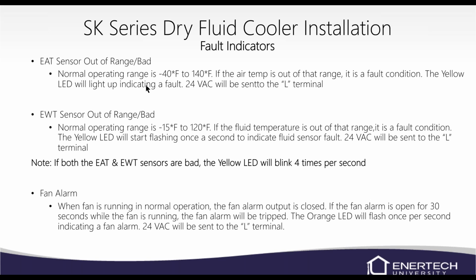There is a fan alarm. When the fan is running in normal operation, obviously the fan alarm output is closed. The fan alarm will have to be open for 30 continuous seconds while the fan is running for the fan alarm to be tripped. And that's an orange LED, and it's going to flash similar to a heartbeat, so once per second. Again, you will get a 24-volt signal to your L terminal as well.